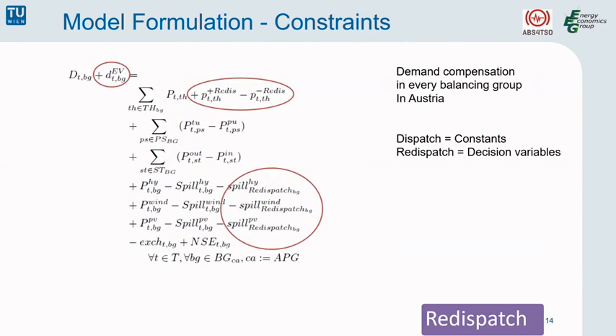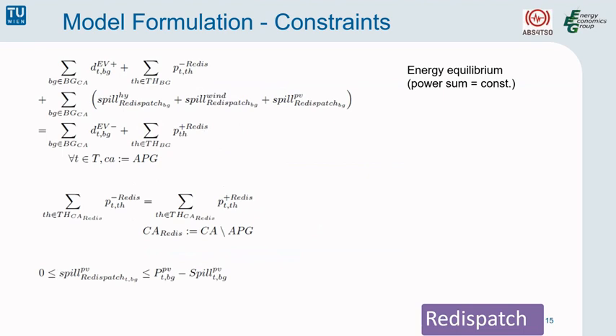The demand compensation has to be considered again, but now all the variables that were decision variables within the dispatch step are constant values. So if a congestion occurs, it can only be resolved by regulating these redispatch variables. There is also a new equation, the energy equilibrium, stating that power generation before and after the redispatch has to be constant. So the demand side management demand increase plus the power plant generation decrease and the renewable energy curtailment has to equal the demand side management demand decrease and the power plant increase.